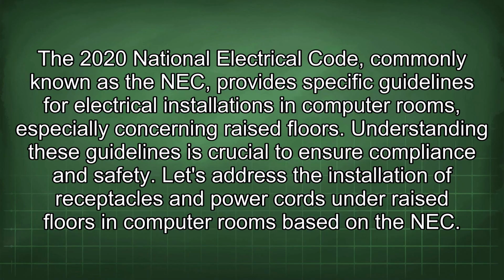The 2020 National Electrical Code, commonly known as the NEC, provides specific guidelines for electrical installations in computer rooms, especially concerning raised floors. Understanding these guidelines is crucial to ensure compliance and safety. Let's address the installation of receptacles and power cords under raised floors in computer rooms based on the NEC.